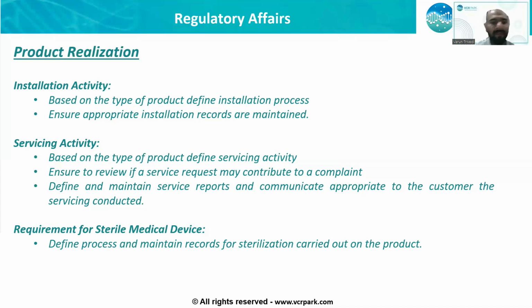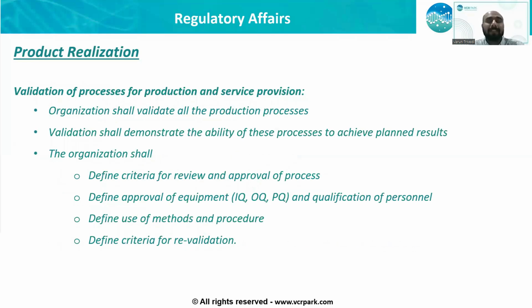Requirements for sterile medical devices. If your device is something that needs to be maintained in sterile condition, then the requirement for the same shall be defined. The processes for the same shall be developed and adhered to. Validation of processes. All the different processes that might be involved in the production of your device shall be properly validated. Installation qualification, operational qualification, and performance qualification shall be conducted, and the relevant and right people shall be identified and trained in carrying out these processes.